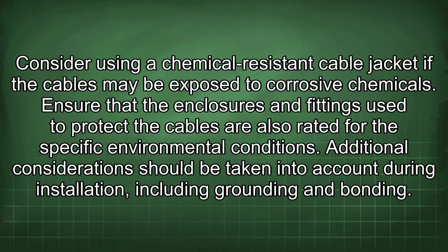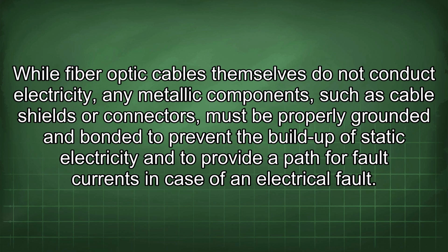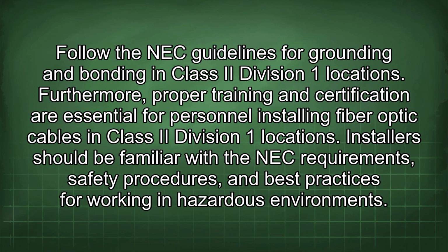Additional considerations should be taken into account during installation, including grounding and bonding. While fiber optic cables themselves do not conduct electricity, any metallic components, such as cable shields or connectors, must be properly grounded and bonded to prevent the buildup of static electricity and to provide a path for fault currents in case of an electrical fault. Follow the NEC guidelines for grounding and bonding in Class Roman 2 Division 1 locations.